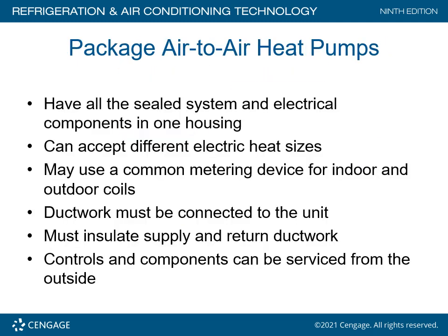Package air-to-air heat pumps have all the sealed system, electrical components in one housing. In other words, it's like a package unit. Can accept different strip heater sizes. May use a common metering device for the indoor-outdoor coils. Ductwork must be connected to the unit in this case. Must be insulating the supply and the return ductwork. No exceptions. Controls and components can be serviced from the outside.